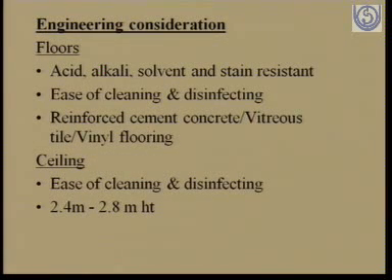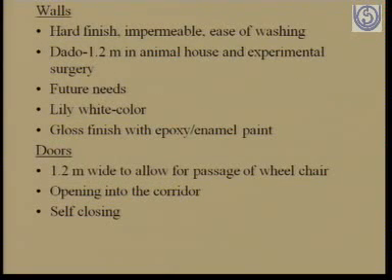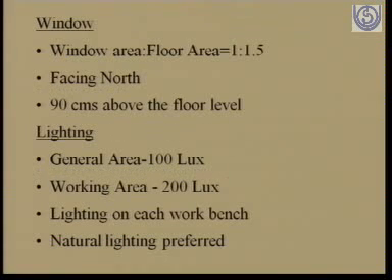As far as the floor is concerned, it should be acid and alkali resistant. Ease of cleaning should be there because of the workload. Disinfection has to be carried out regularly. So it is recommended that cement concrete reinforced floors or vitreous tiles are the in thing nowadays. The ceiling should be easily cleanable. Walls should have a hard, impermeable finish. Ease of washing should be there, and future needs have to be taken care of. Doors should be wide to allow passage of wheelchairs, and self-closing doors are required.